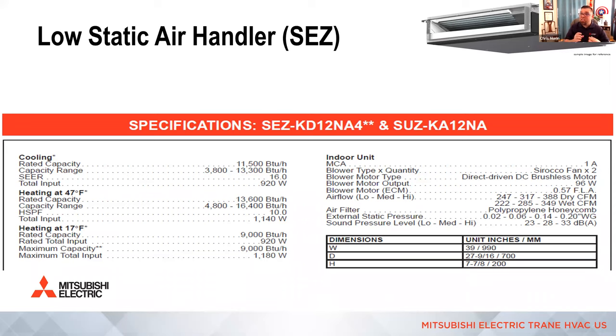So we will actually limit the volume of air and the static pressure with that ECM motor. It's not like a PSC motor where we have 4 speeds and the static pressure will reduce the volume of air. The only time we will reduce the volume of air is if we get above that maximum static, because it's an ECM motor, all right? Hopefully that answers your question. Ideally, we'd love to have infinite choices, right? But we can't, we have to pick a few.